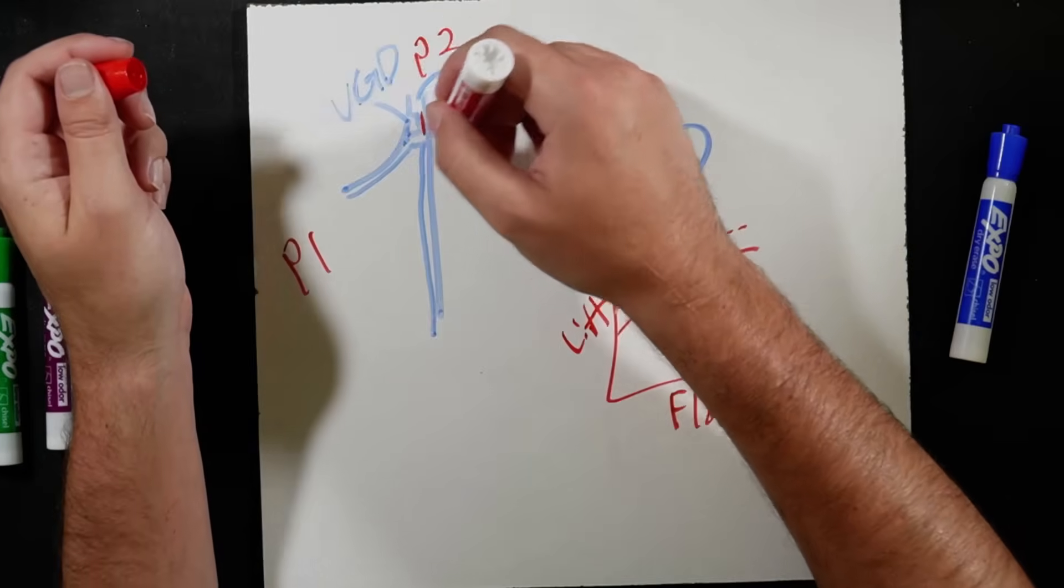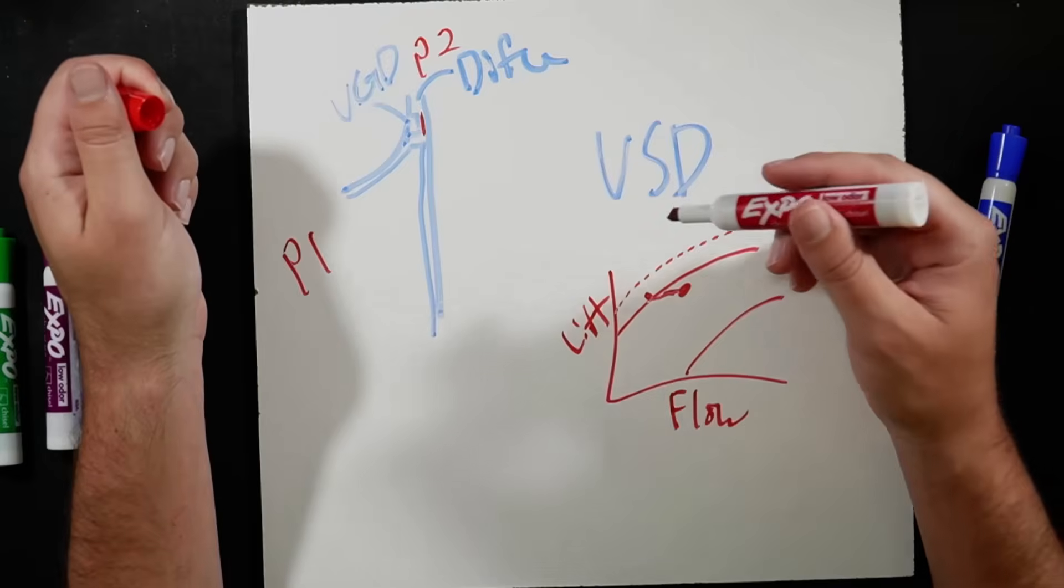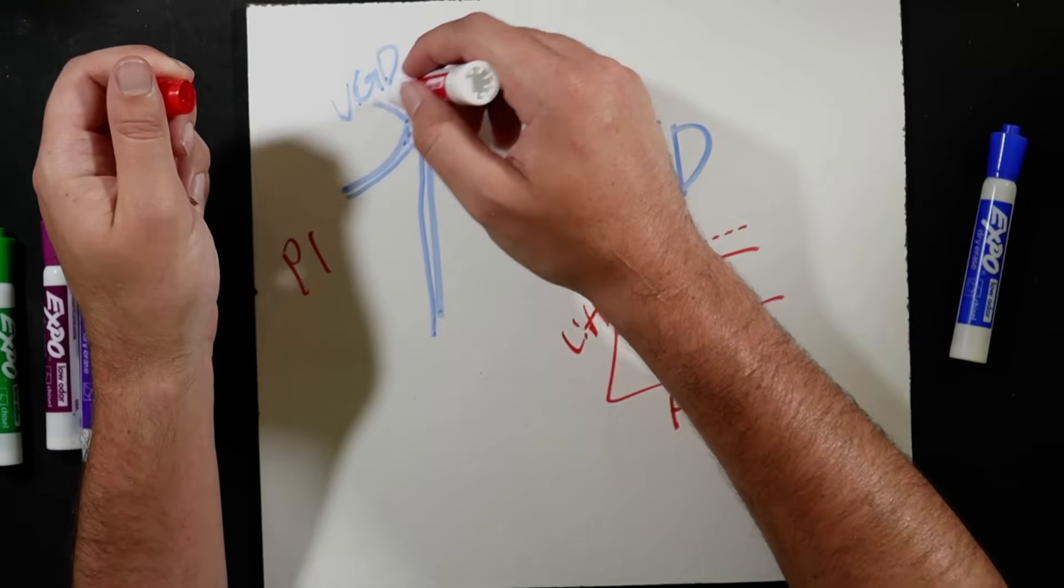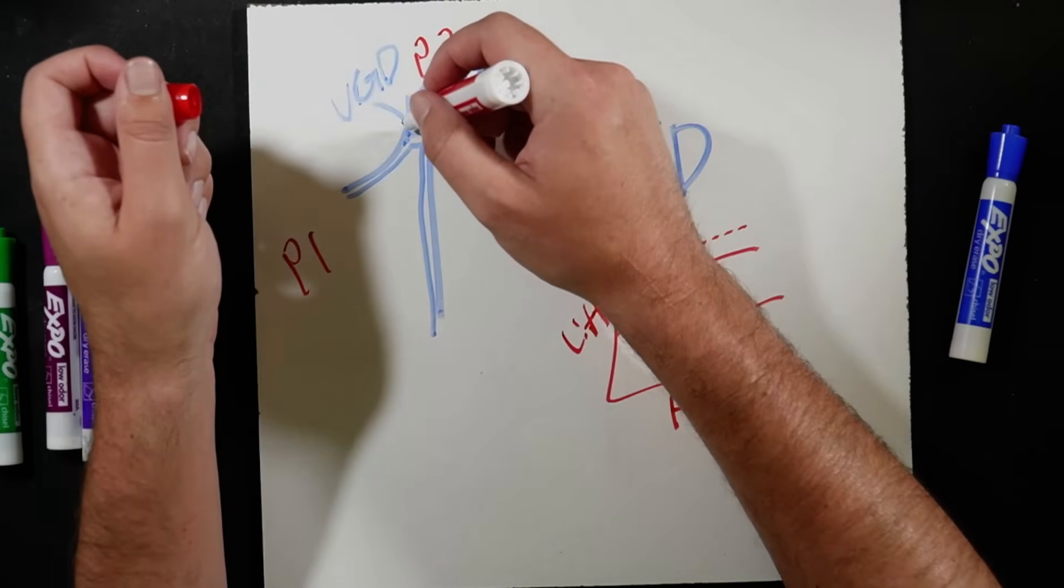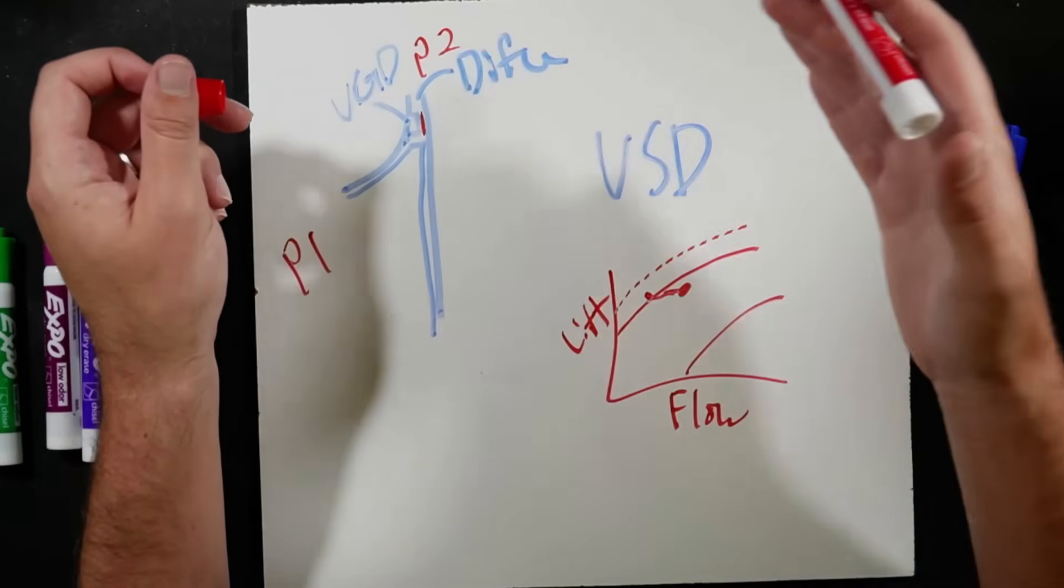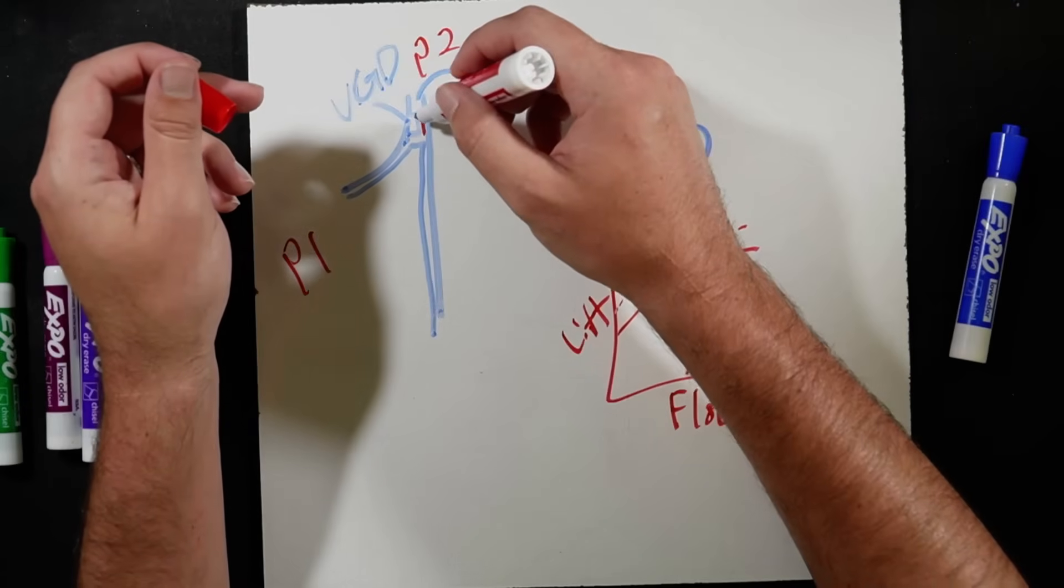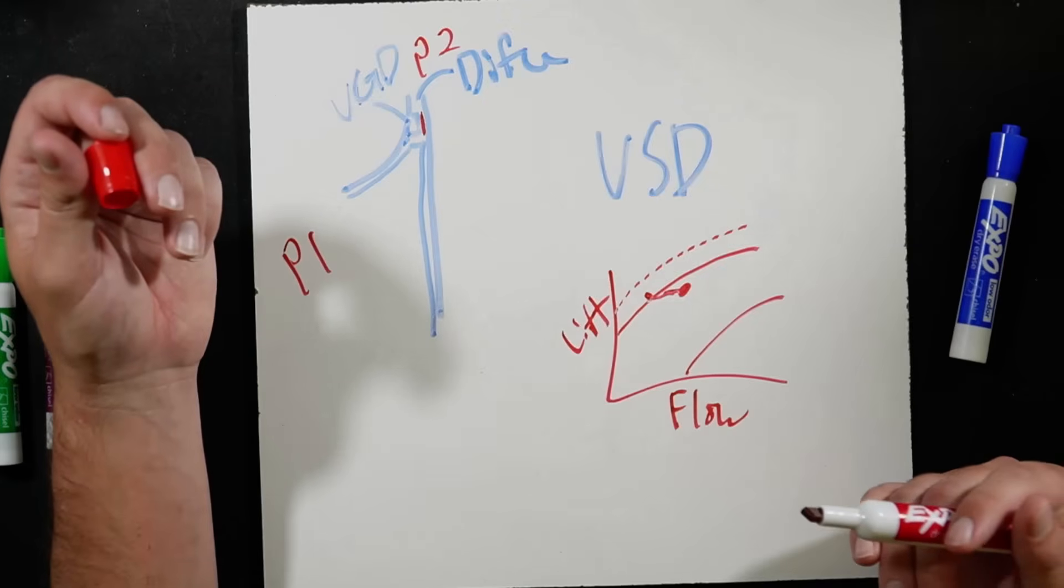And that is why some of these chillers do not have an inlet guide vane, an IGV. They only have a VGD with a drive. And part of that VGD process is as that chiller is unloading, we push the VGD to a closed position, which narrows our diffuser gap, reducing how much flow goes through there.